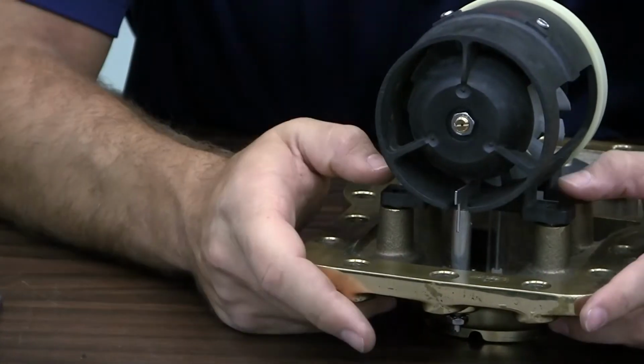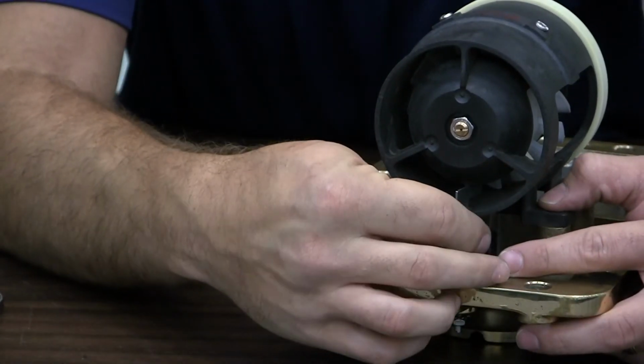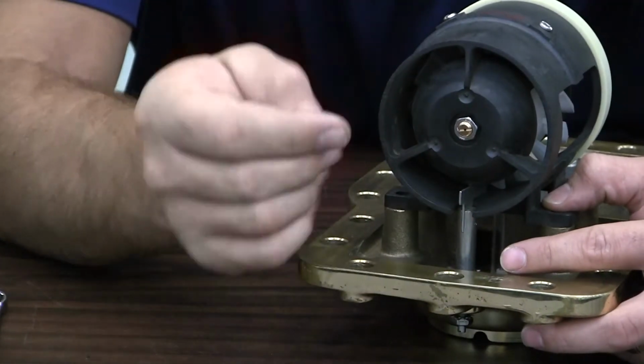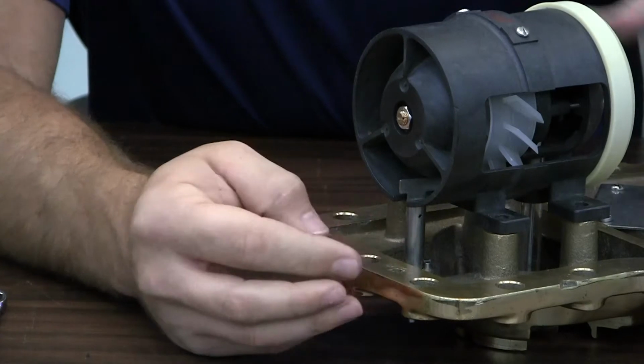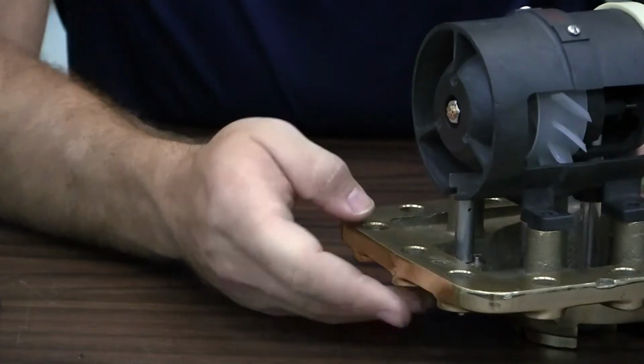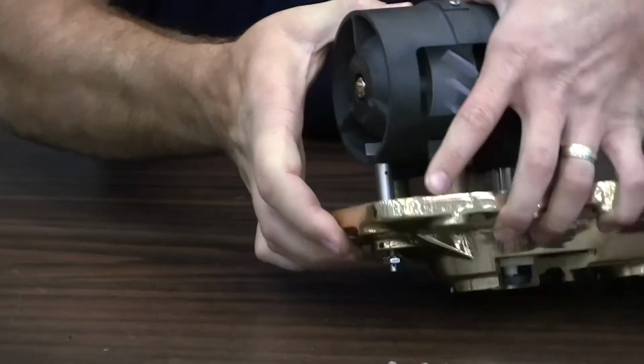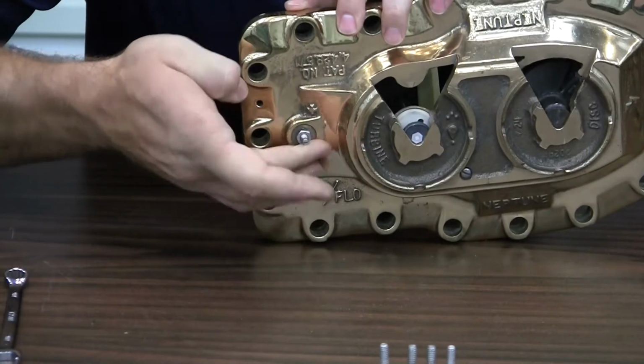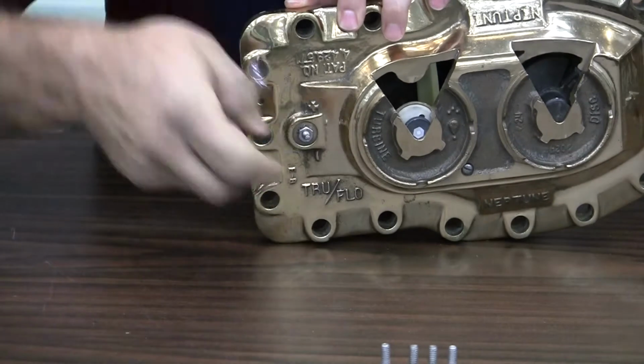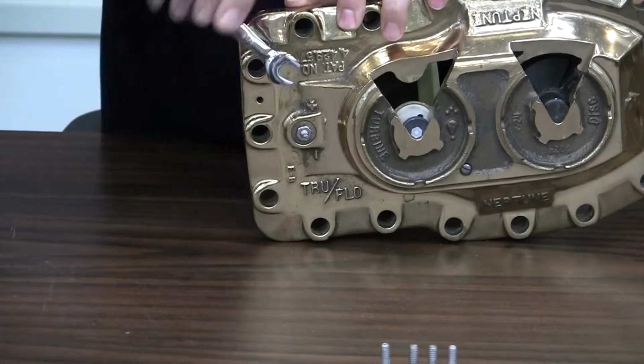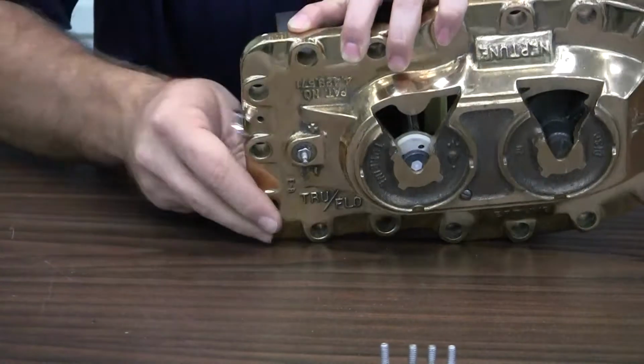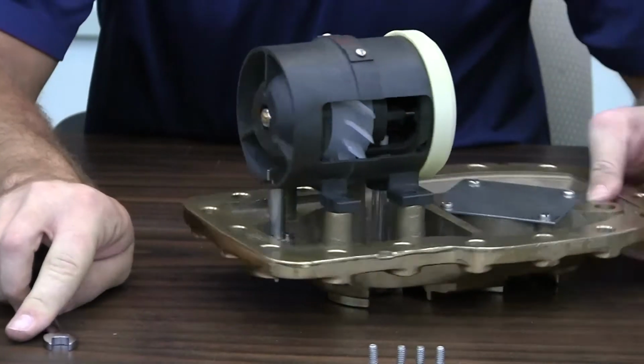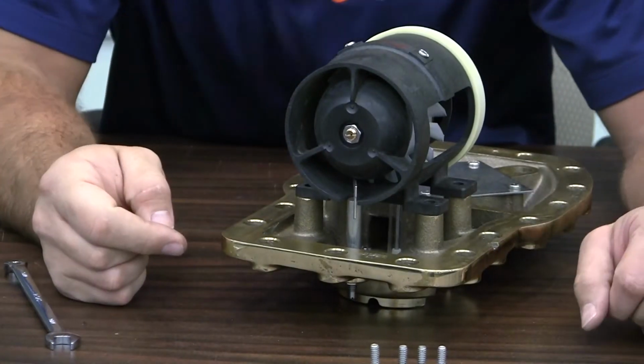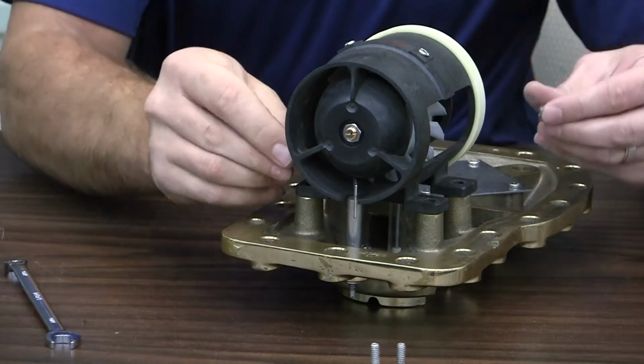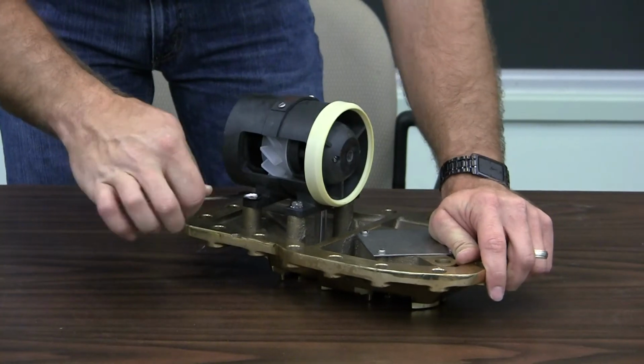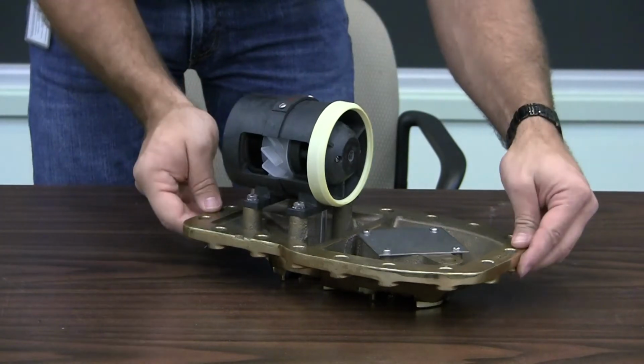Now, before you tighten your calibration vane, it's important that you set the calibration vane to the center. That way you know you have it in the middle of the calibration for the meter. So once you do that, you can go to the other side of the meter and tighten down the calibration vane. Once you have the calibration vane tight, you can replace the 4 bolts that hold in the turbine assembly. And we'll do that now. I finished tightening the 4 bolts that hold the turbine assembly onto the cover.